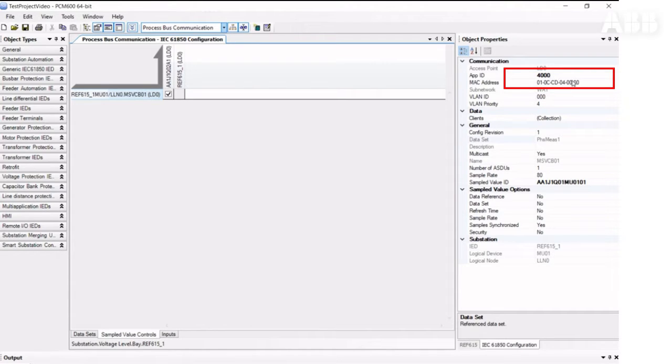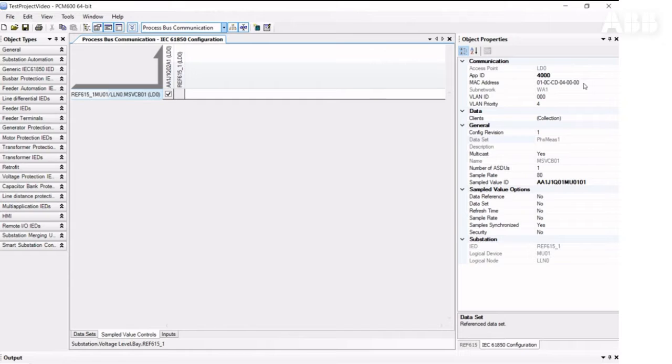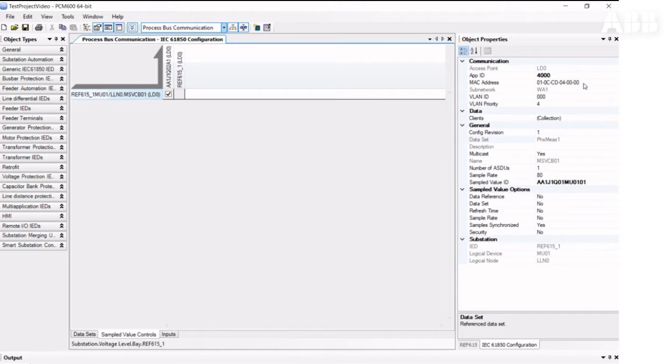The MAC address must be unique within the substation network. The tool keeps the MAC address of the newly created sampled values control element unique within the project. Users can also manually change MAC address values. The VLAN ID can be changed here.